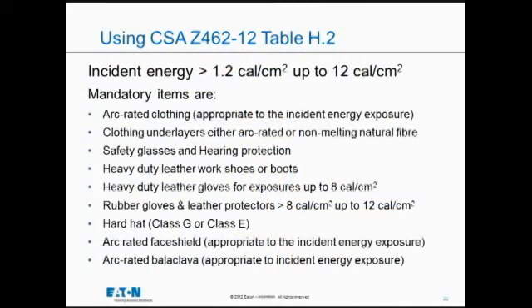There's a little bit of information in the middle there on gloves, and there's some limit to how far you can go with leather gloves on their own. 8 calories is the limit, and after that you must use a rubber glove with a leather protector up to 12 calories, or alternatively an arc-rated glove. So I'll go back to this one. At 1.2 to 12 calories, there's a requirement to wear arc-rated clothing. That's flame-resistant and then tested for its arc-rating capability.